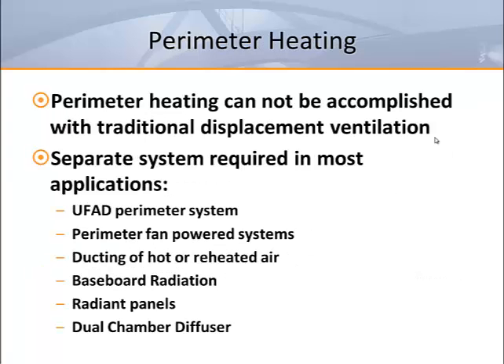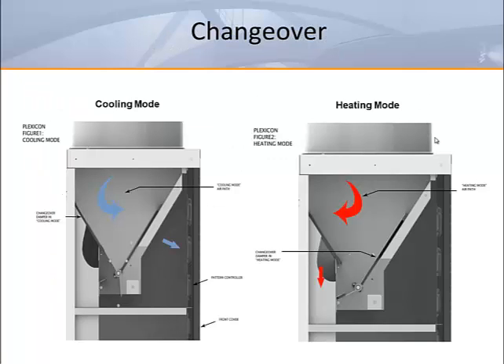Because by design, displacement ventilation works on the principle that buoyancy drops cool air to the floor, it is also true that warm air rises. Thus, displacement ventilation is not effective as a heating device. Typically, heating must be handled with a separate system. One solution might be a dual-chamber diffuser. This dual-chamber diffuser is equipped with a baffle in the plenum to change the direction of supply air to direct it into the room through the displacement face on the top during cooling. During heating, the air is directed to the bottom chamber where a high-velocity jet of warm air is directed across the floor. The supply air is delivered to the outlet with one duct supplying both warm and cool air to the space.